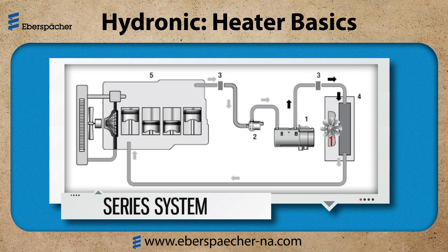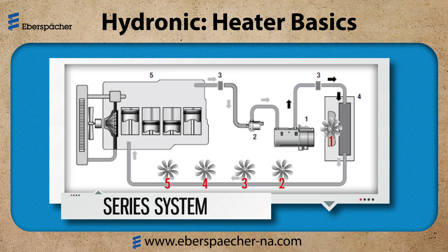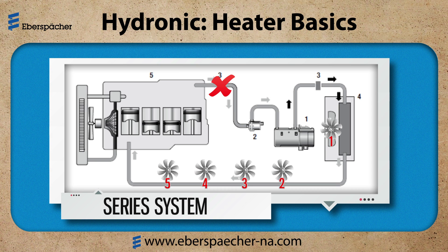To illustrate a point, let's add four more fan units to this circuit. Do you think that fan number one will blow warmer air than fan number five? The answer? Maybe a few degrees. I probably will not feel the difference, but I can measure it. This holds true if I have good coolant circulation. If I have a restriction, like a kinked hose or maybe a restricted fitting or valve, then my coolant is not circulating well and fan number five is definitely blowing colder air than fan number one.